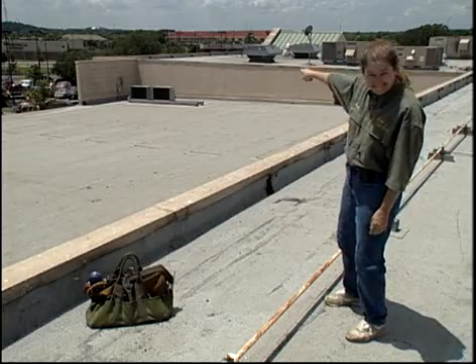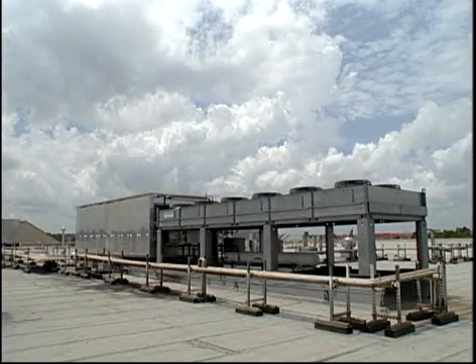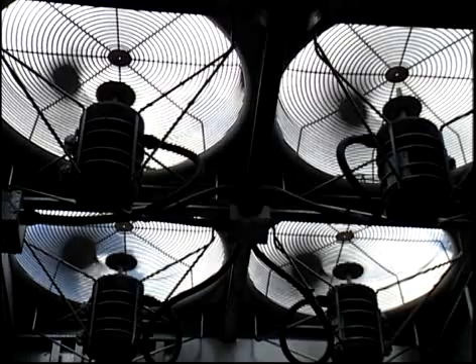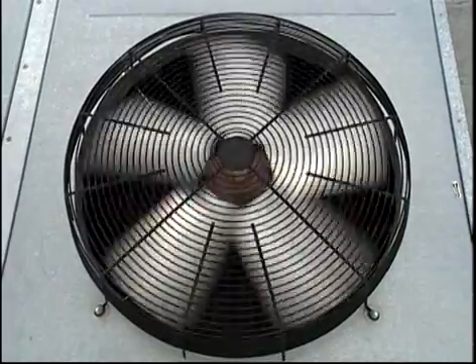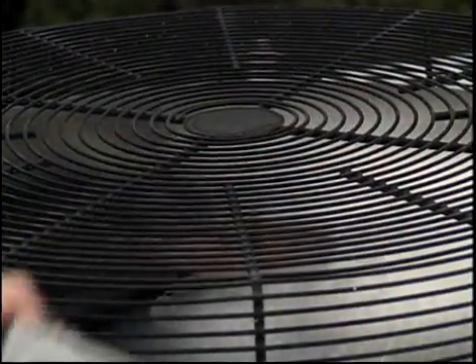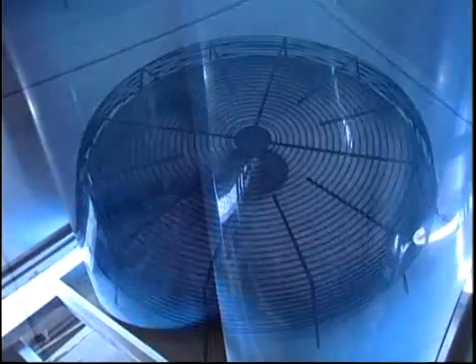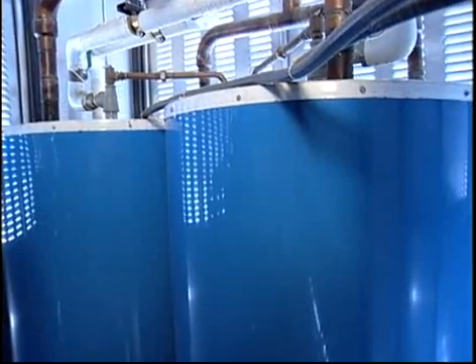Except for those ice machines, which are off in their own little world, all other refrigeration condensing units are centralized here in the rack shacks. For energy saving purposes, the condenser fans only run when necessary, ramping up and down as required by condenser pressures. This is controlled by a separate control called the VSD, or variable speed drive. Another energy saving device is the recycling of hot water, heated by the condenser coils and stored in hot water tanks for use elsewhere.